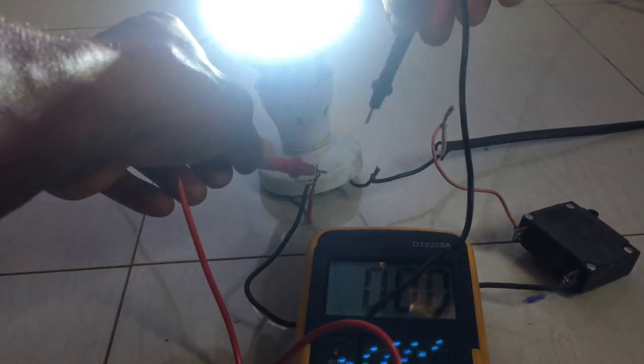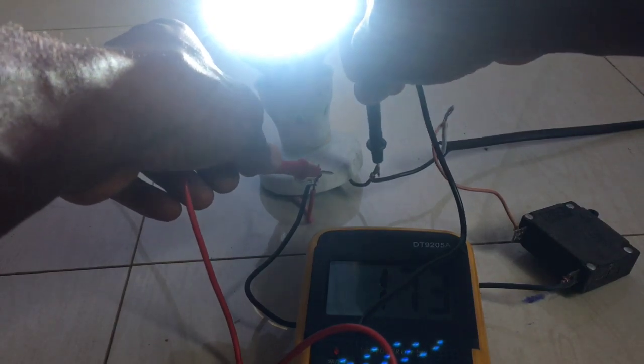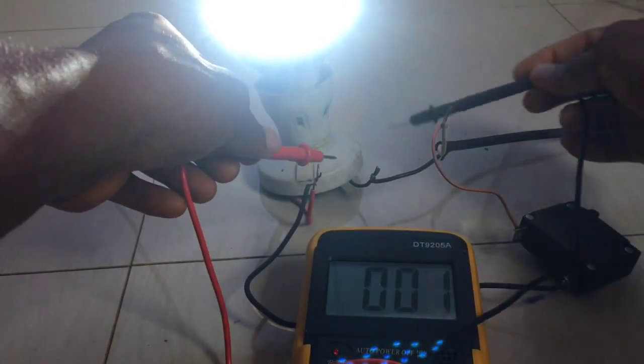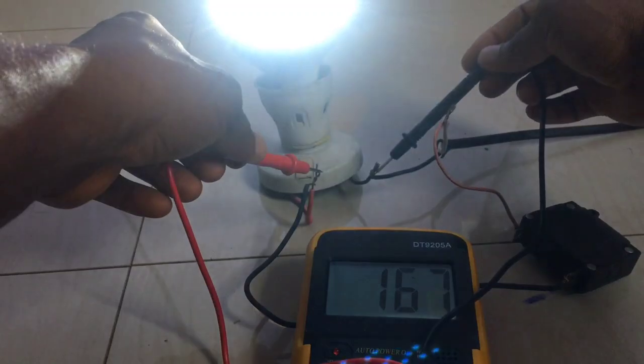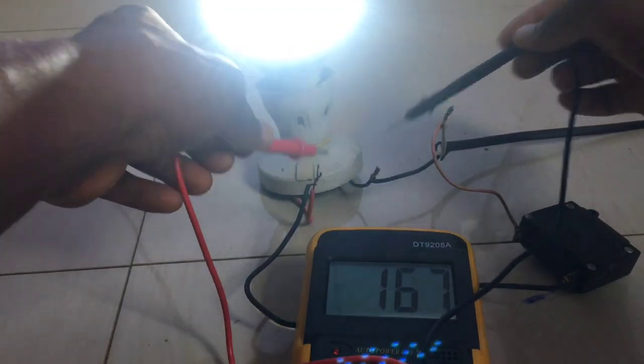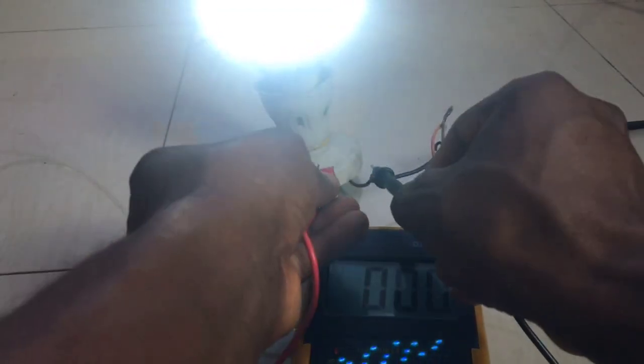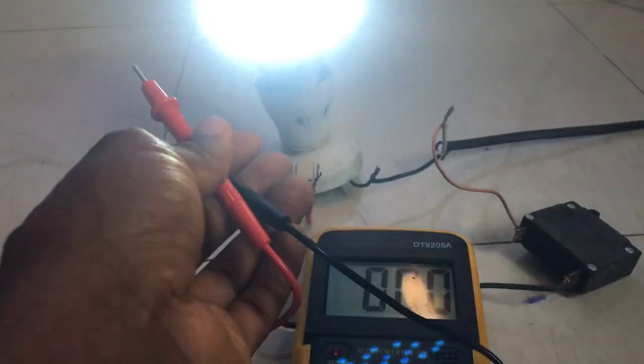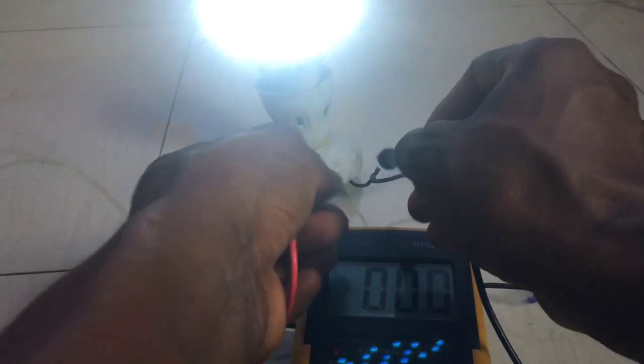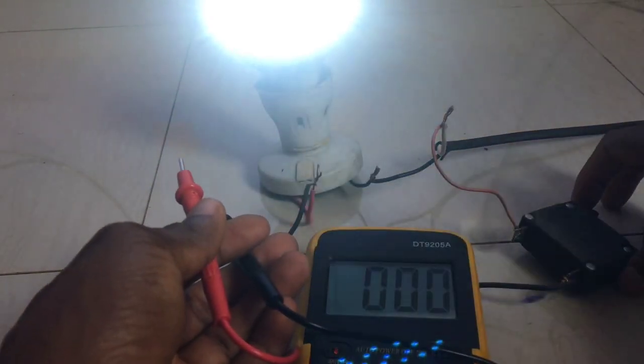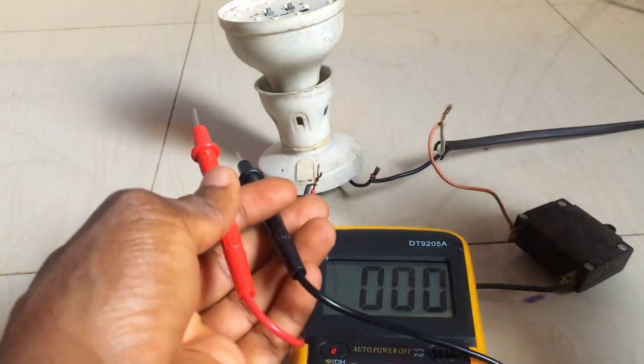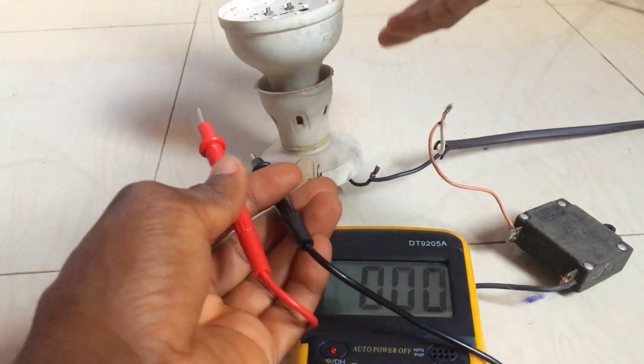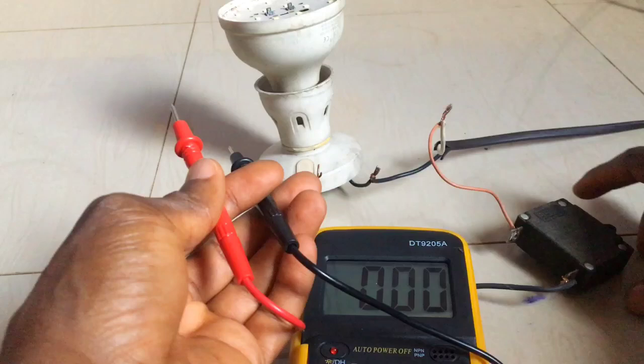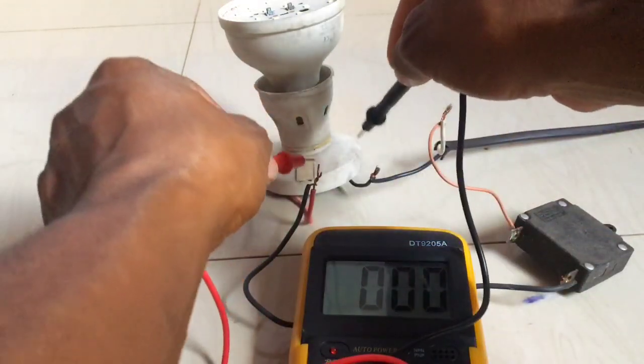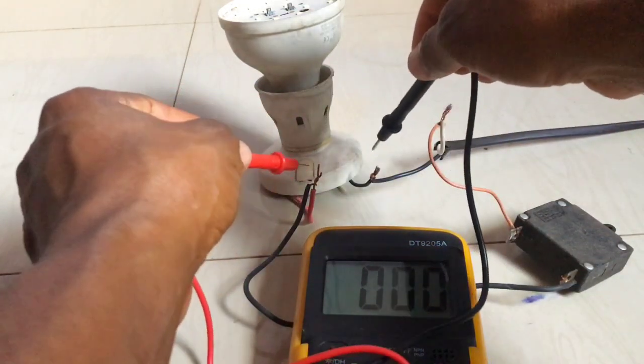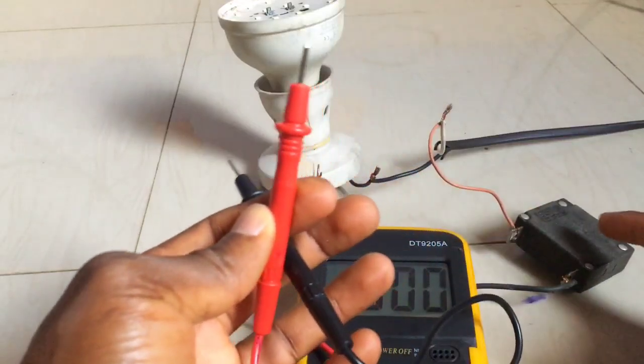As the switch is on right now, if we check, we're going to get some voltage reading. As you can see on the meter, we are having about 160 volts AC. So if you are getting voltage at the lamp holder terminal and yet your bulb doesn't turn on, bear in mind that it's either the bulb is burnt out or your lamp holder is bad. But if your switch is on and you don't get a voltage reading at the lamp holder terminals, then know that something is wrong with your switch.